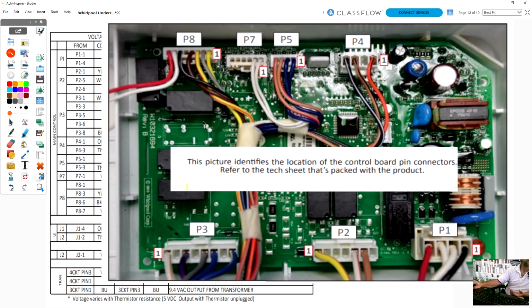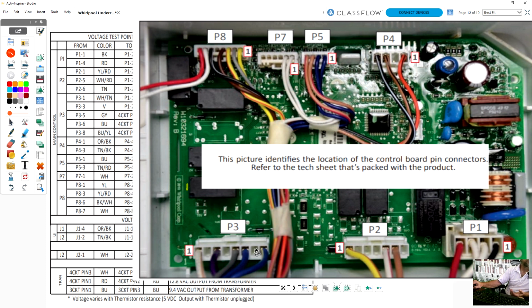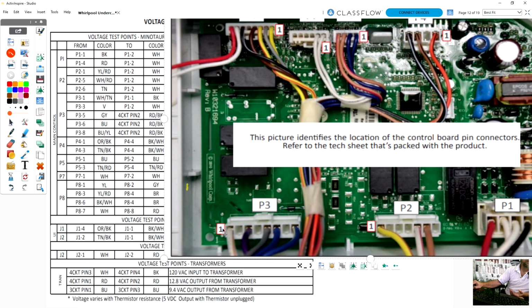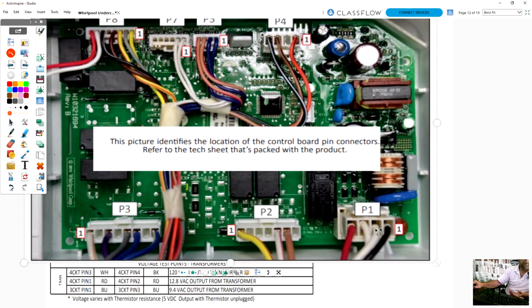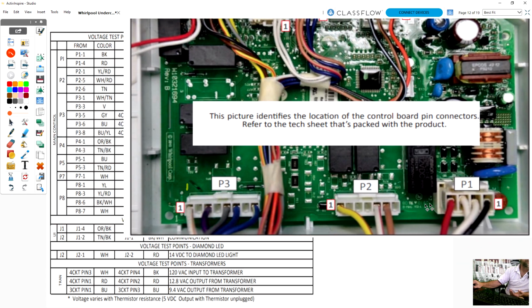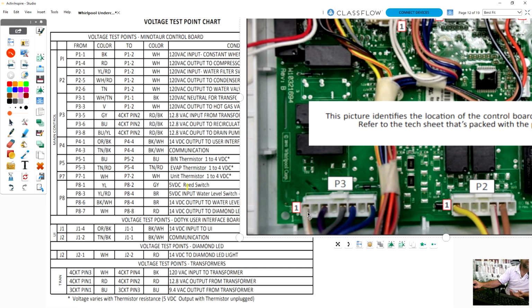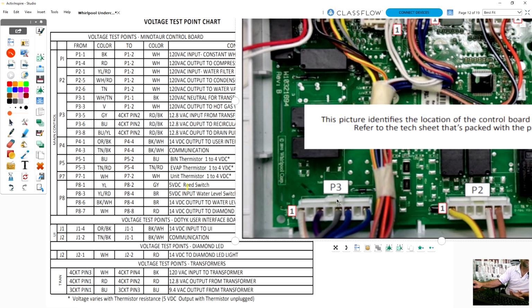So what that means is I find plug 3 here, and notice they are giving you a number 1 here. There's usually a red dot or number 1 printed on the board, but they might have covered them up. This number 1's on the opposite side. What that little number 1 means is that this first wire's pin 1. There's no wire on pin 2. Here's pin 3. So they want you to check P3-1 and P3-3. P3 means plug number 3, pins 1 and 3. So you're going to put your meter lead on this one and this one for 120 volts.